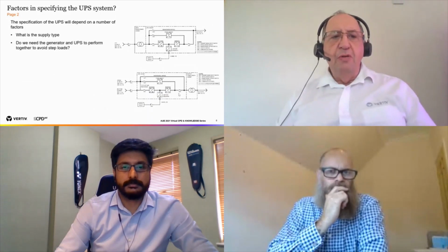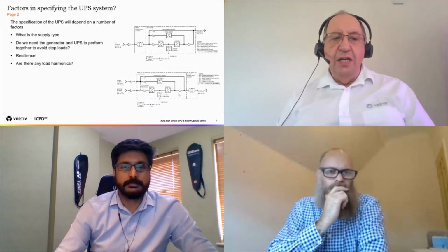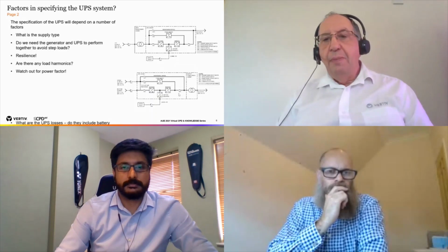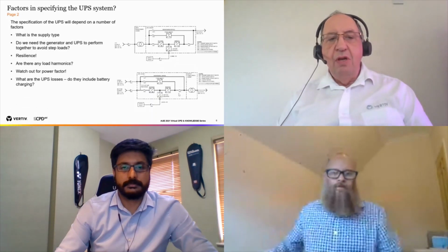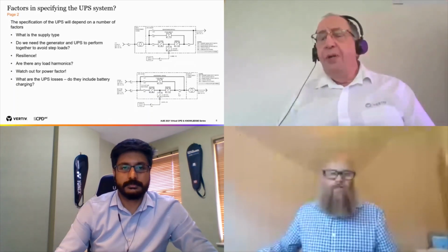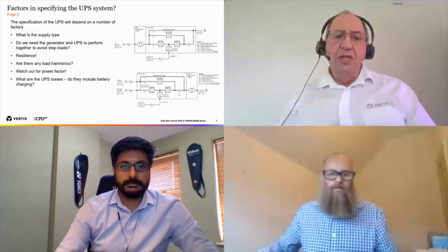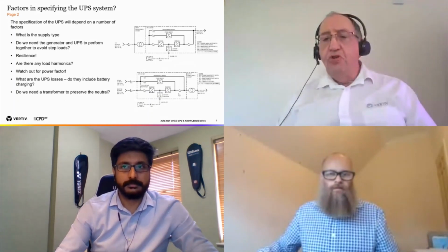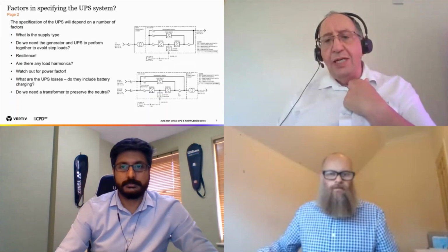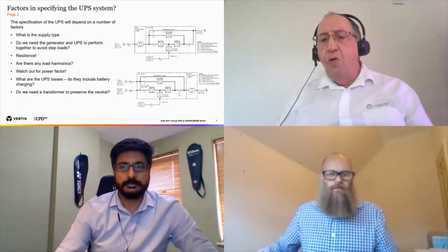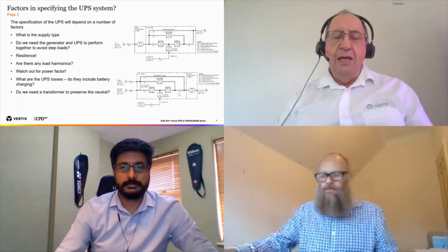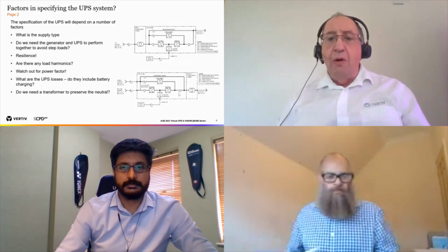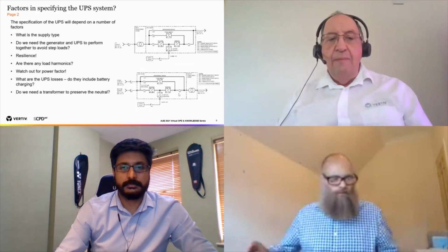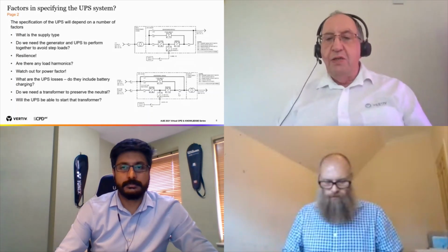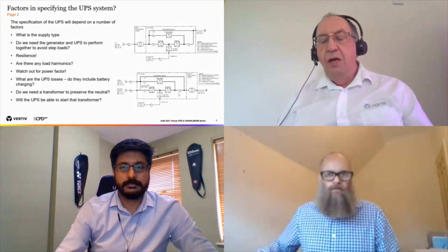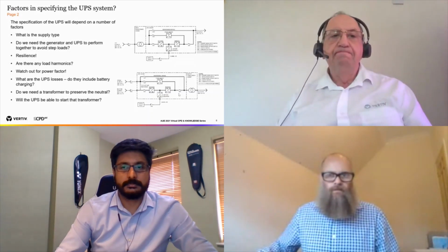So supply type we've mentioned. Do we need a generator? Resilience? Are there any load harmonics? Power factor is something we've got to think about. UPS losses. Cheaper UPSs tend to have bigger losses. Do we need to put a neutral in? That's the bottom diagram on the right hand side, so that the transformer preserves the neutral, and we've got a 3-phase without a neutral supply into the UPS. And we've got to engineer the UPS to be able to energize the transformer, obviously, to get it up and running.